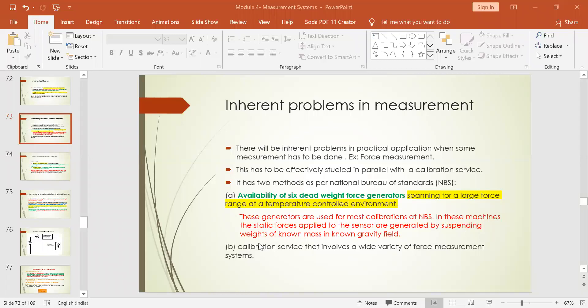Welcome back. We were dealing with the inherent problems in any measurement. The second methodology is the actual calibration service: you measure a known standard material, check the force value, then replace that standard material with the actual material whose force measurement has to be done, and compare. This way you overcome the inherent problems associated with measurements.